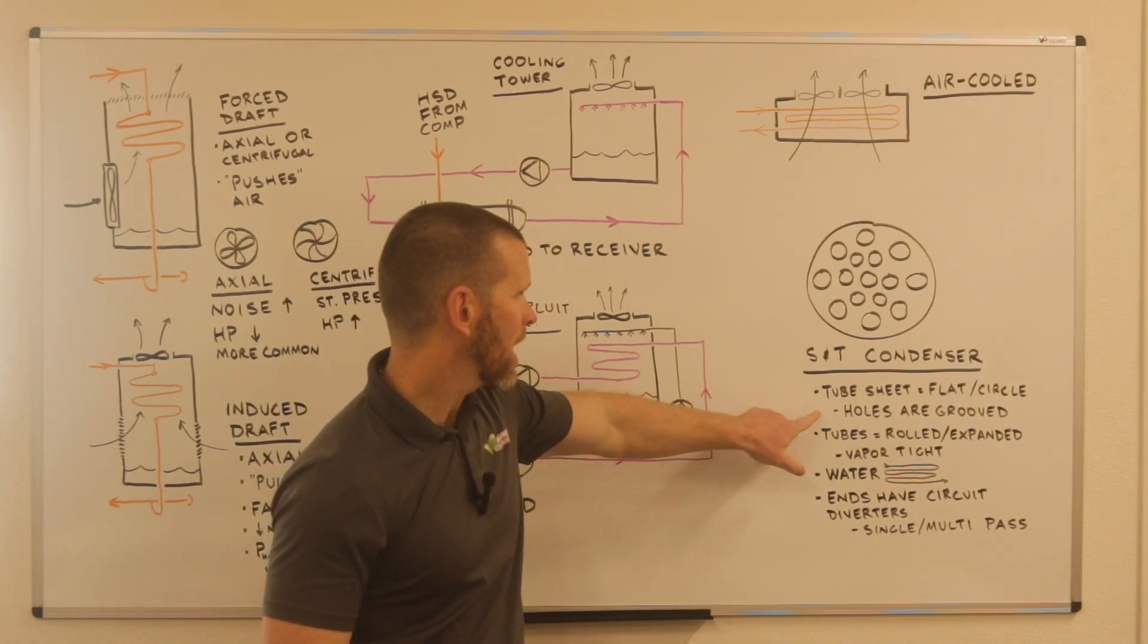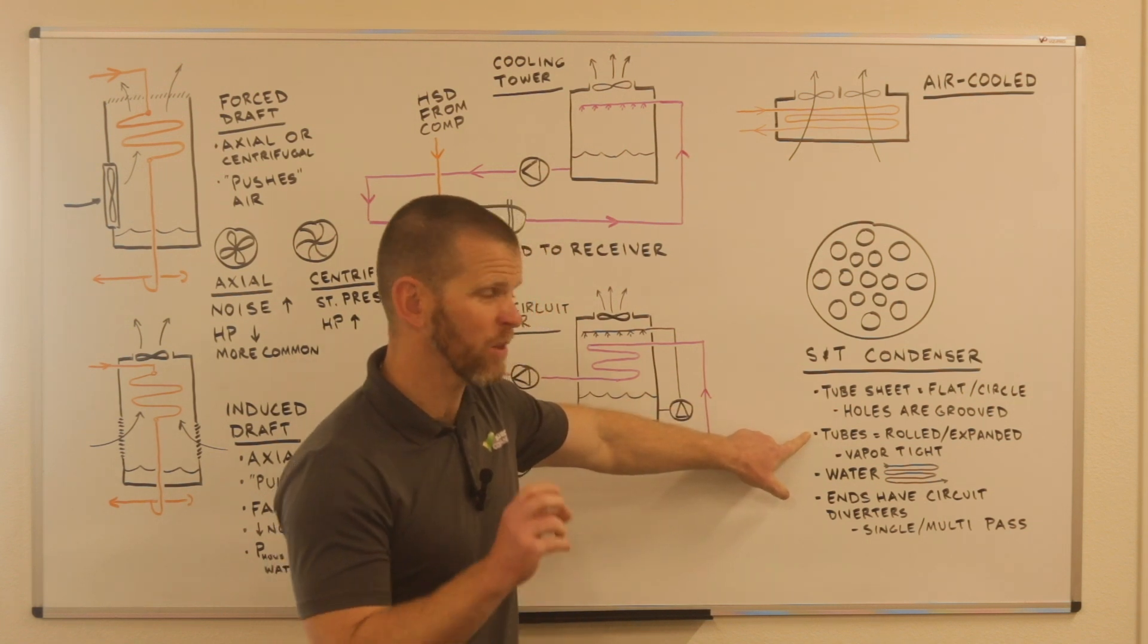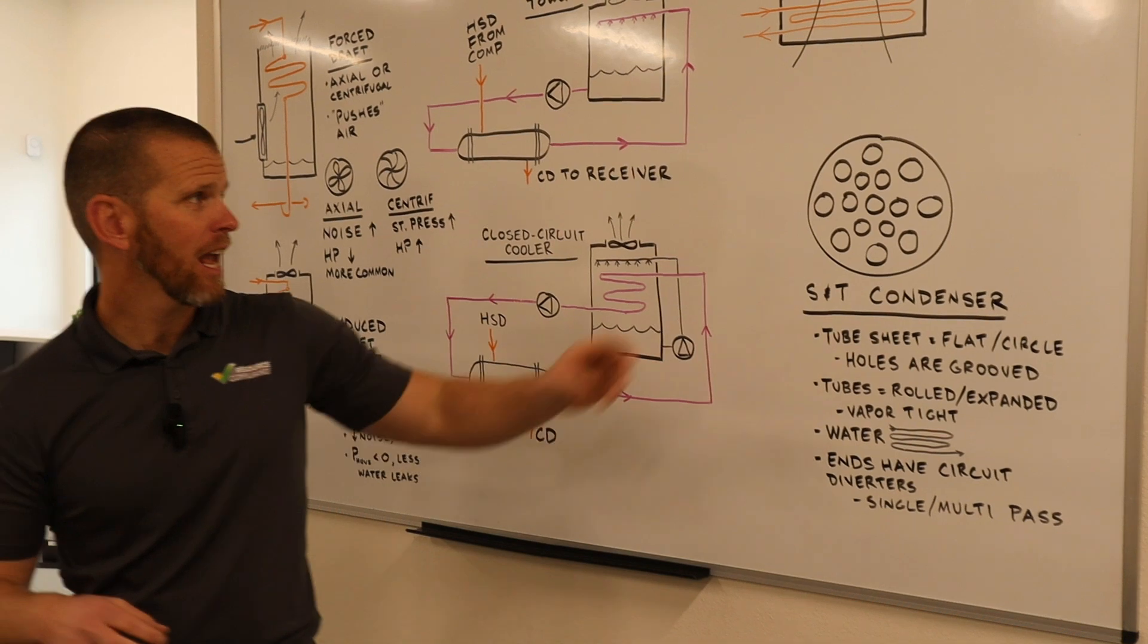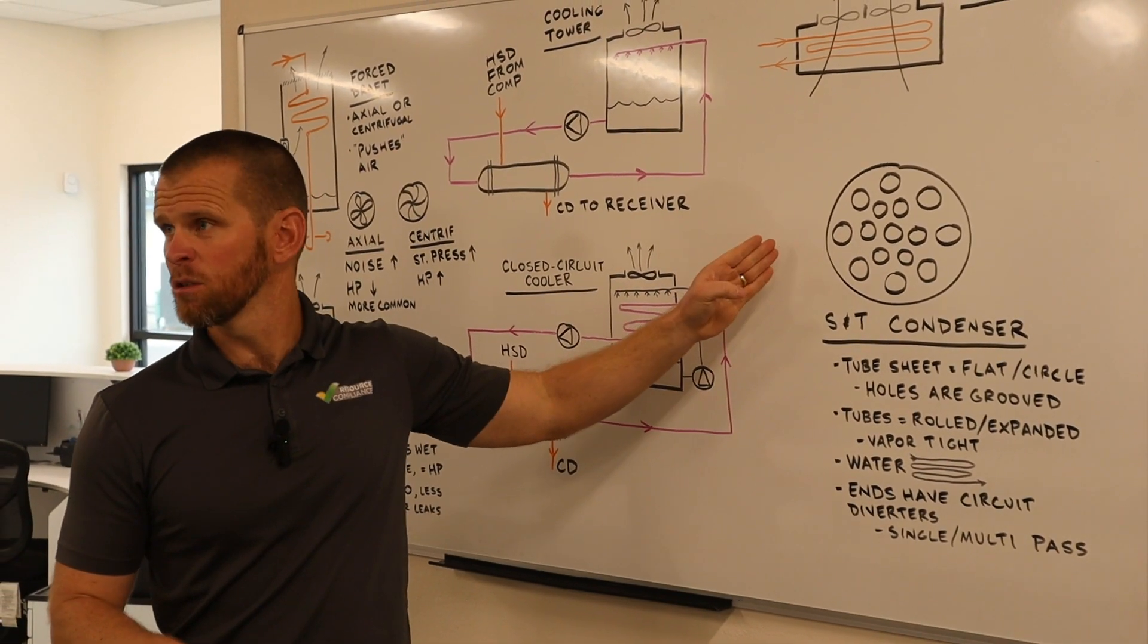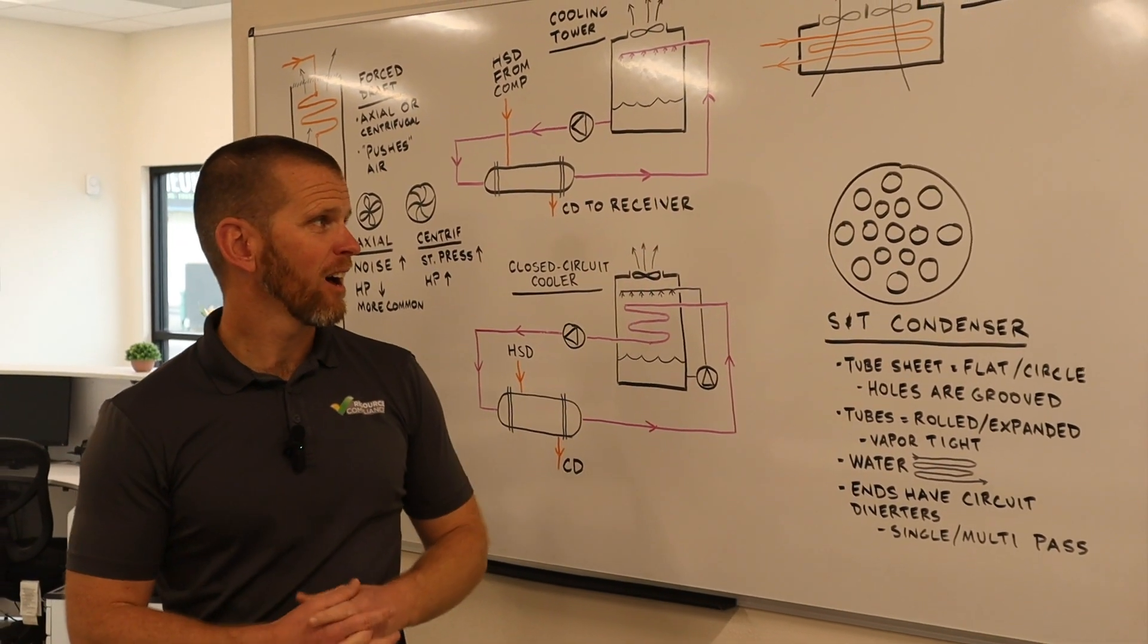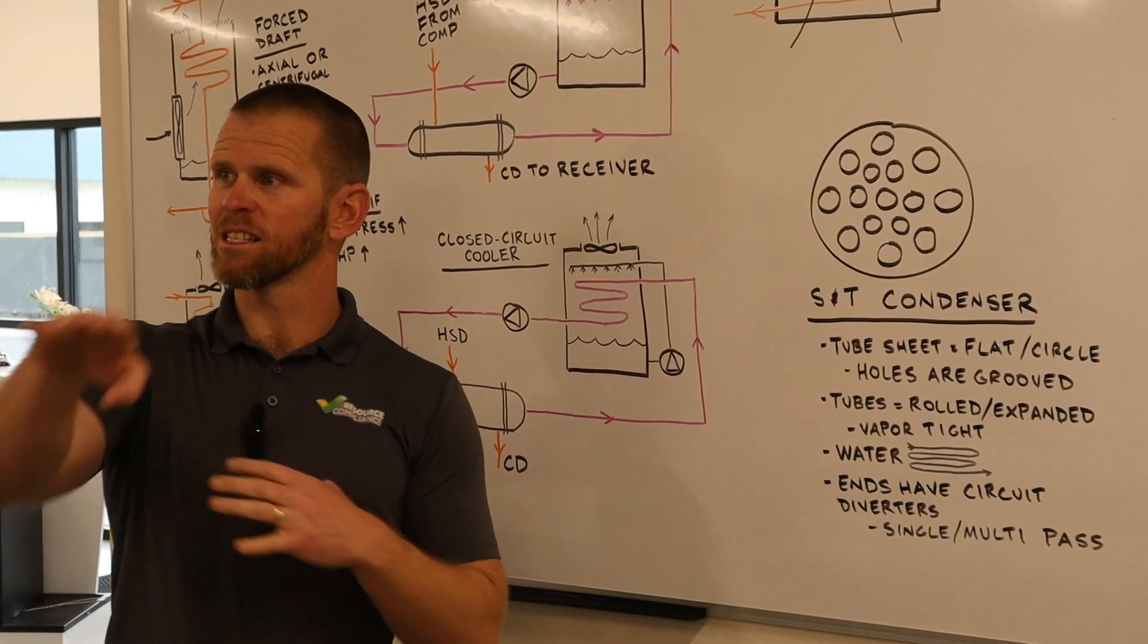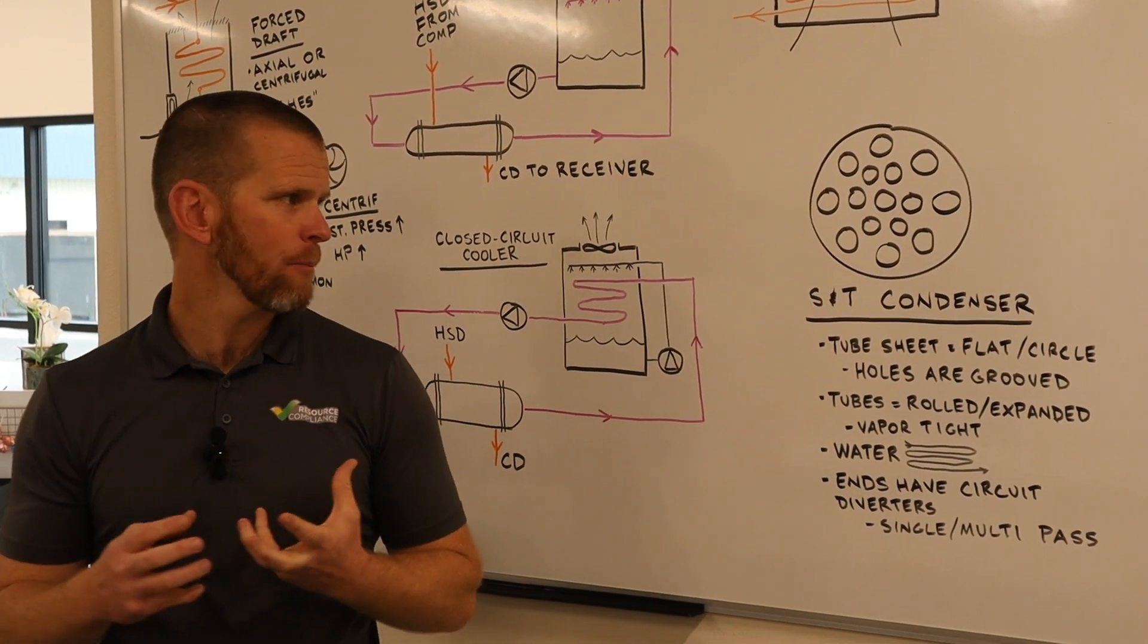The tube sheet's flat and the holes are grooved because then when the tubes are rolled and expanded, it creates a vapor tight seal. There'll be at least two tube sheets, one on each end that the tubes, the bundle of tubes sometimes it's called, fits into and secures them.